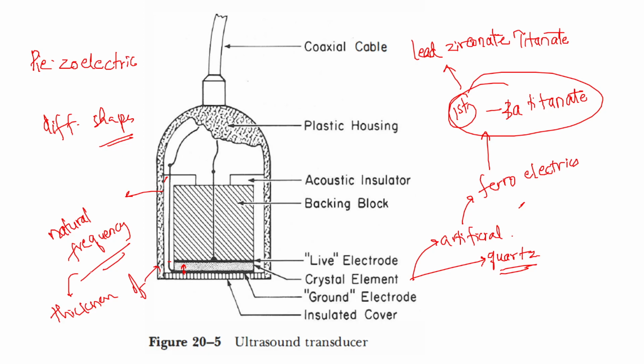So this thickness of this piezoelectric crystal is designed so that its thickness is equal to half the wavelength of ultrasound to be produced by the transducer. The crystal will resonate, oscillate at the frequency based on its thickness. And the frequency at this thickness corresponds to half of the wavelength thickness, and this frequency is called the fundamental resonance frequency. The frequency of a piezoelectric material at this half wavelength thickness is called the fundamental resonance frequency.